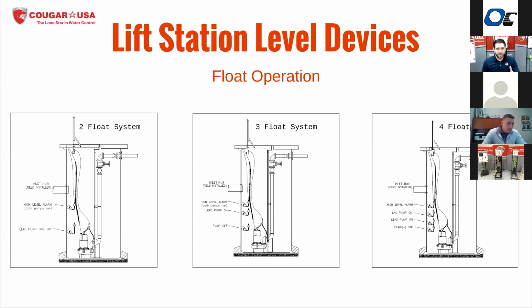Okay. So that's a three float system. Onto the four float system. Now what we've done is we can actually separate out the lag pump from the high level alarm. So our bottom float now is all pumps off, then lead pump on, lag pump on, and then our high level. So this really gives you the ability to run both pumps without getting your high level alarm, as well as extend the pumping range of your lag pump as well as your lead pump.